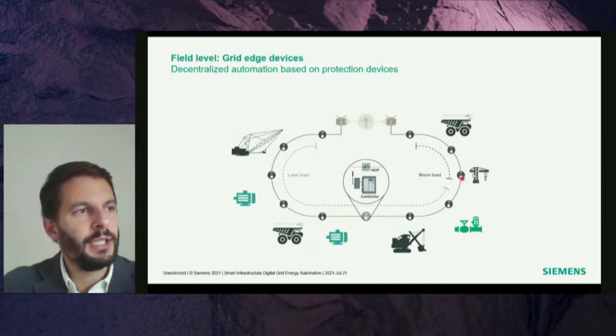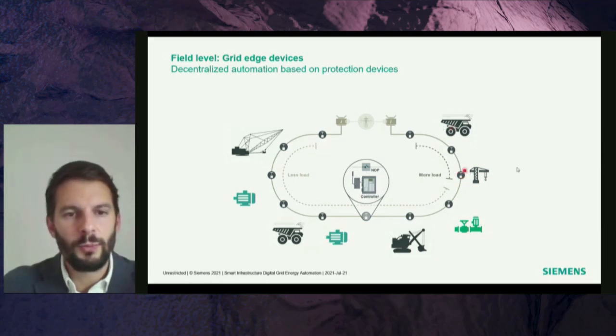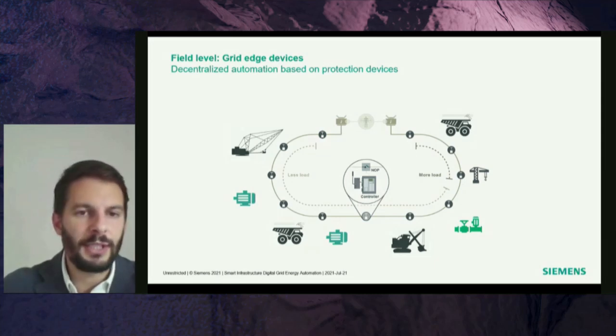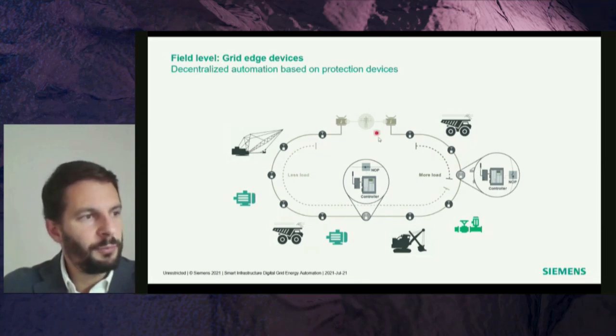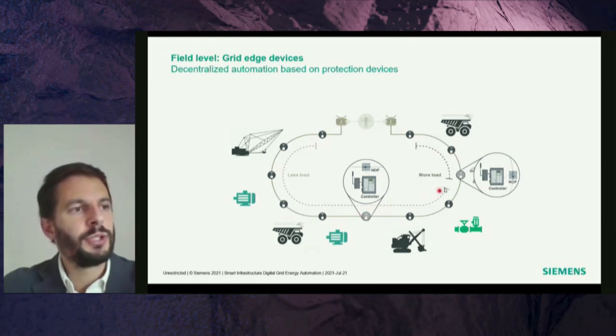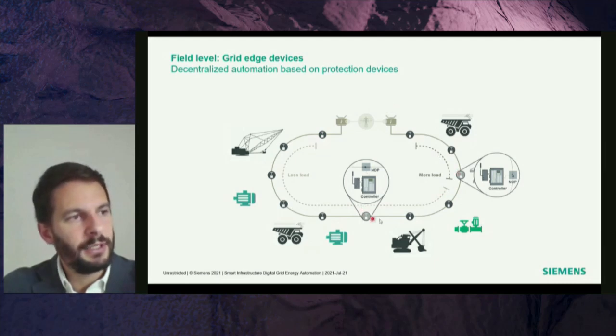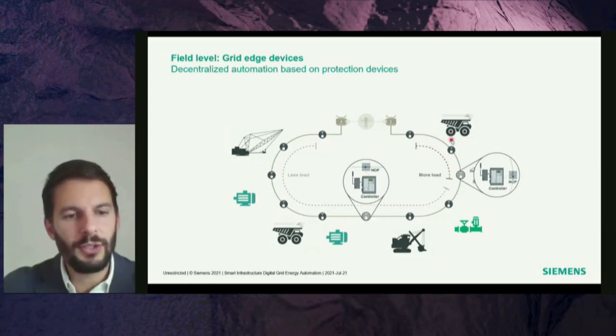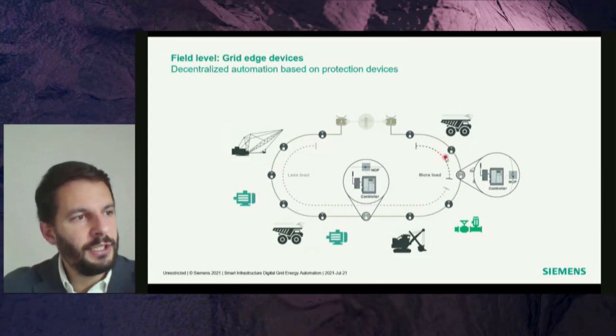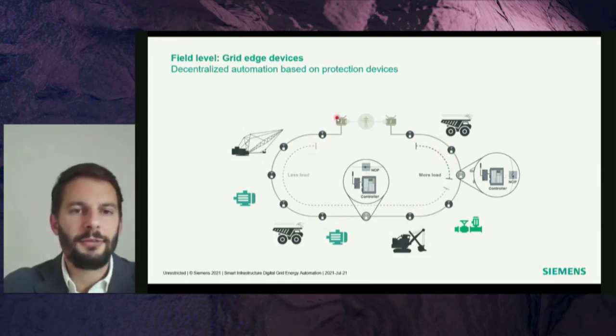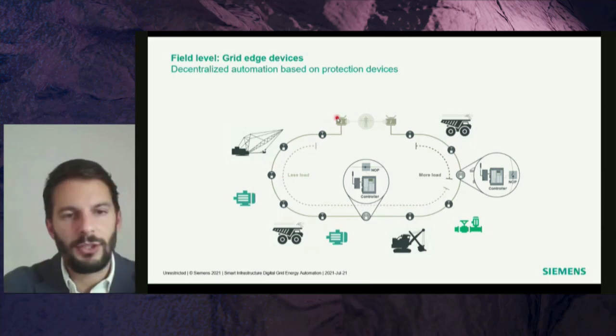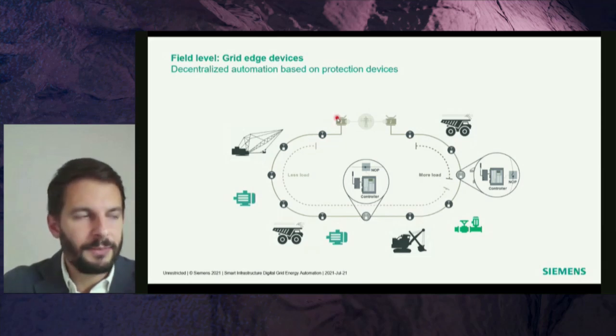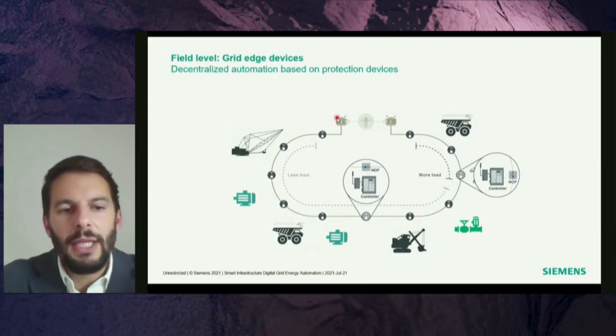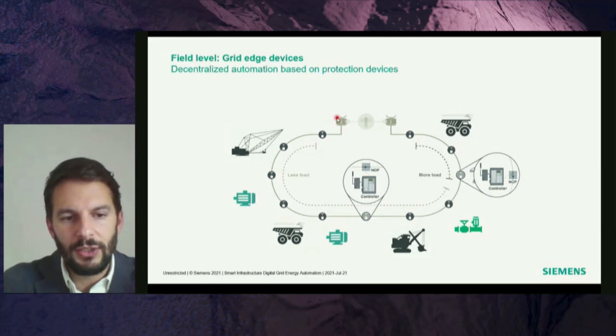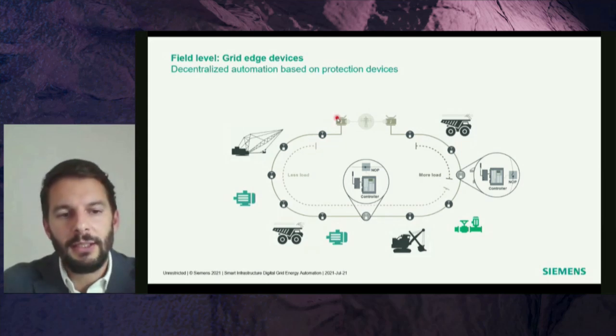So what are the devices looking to perform? To stabilize the load through the entire grid infrastructure by shifting the position of the normally open point from the middle of the loop to close to in-feed point B. This immediately reduces the loads coming from the right-hand side, reducing the potential overload scenario, and safely increases the loads coming from source A, assuring the grid is properly stabilized dynamically without any intervention from a SCADA operator. These are two relevant application cases for grid edge automation: protecting and securing loads from outage events, and protecting the system from overload situations.